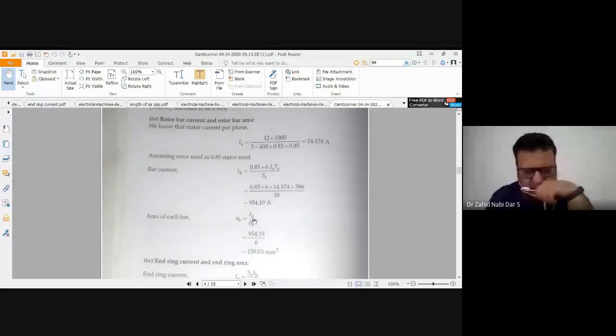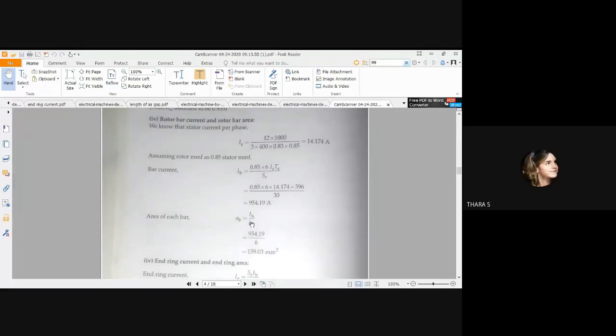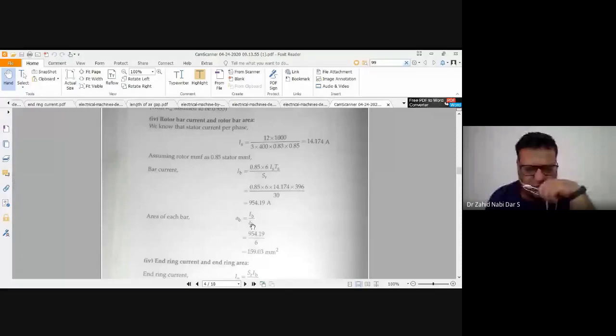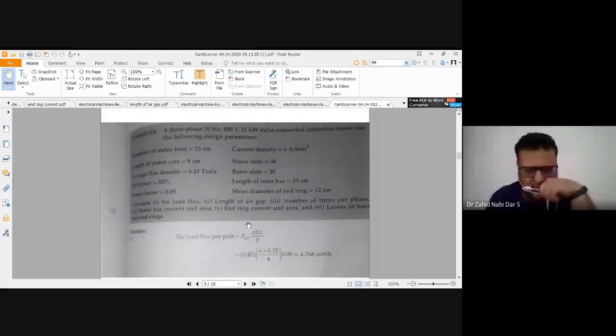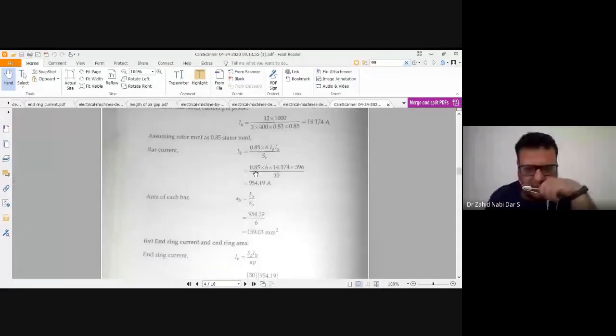Now the area of each bar you can calculate from the current density. What is this term called, gamma B or rho? Delta B, yes, del B. Please switch off your mics. Del B, the current density, would be equal to current divided by area. So your area AB would be equal to IB divided by del B. IB you just calculated, 954.19, and del B, the current density, is given as 6 ampere per millimeter square. Substituting 6, it happens to be 159.03 millimeter square.